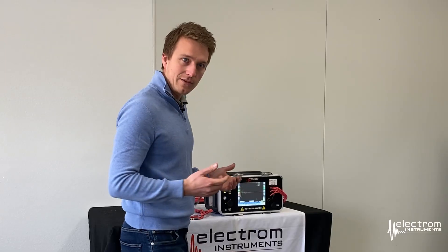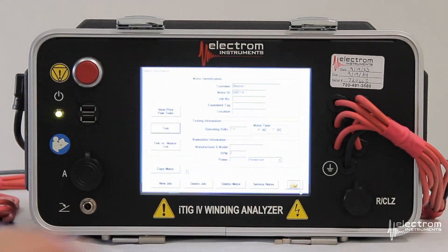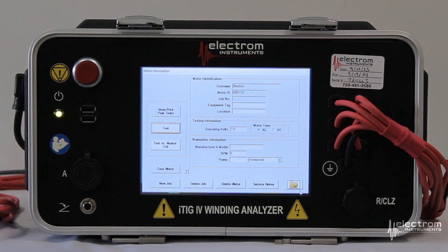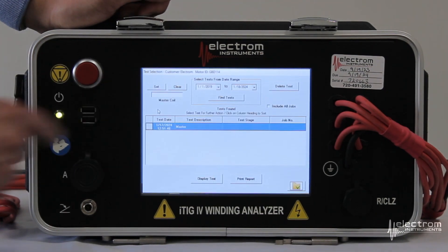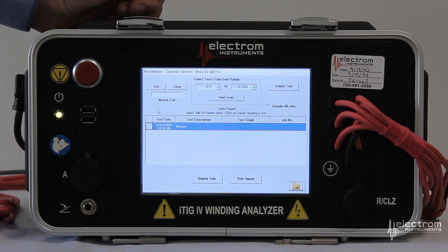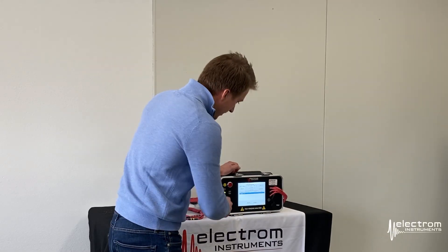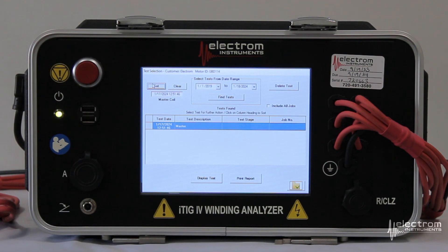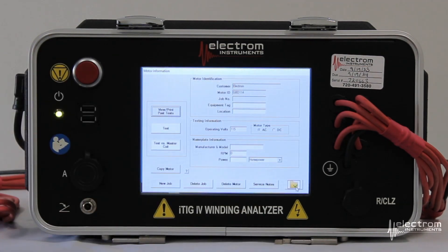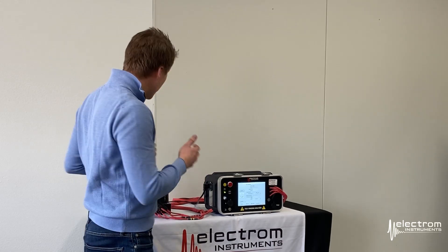Now we'll see what this looks like when we save it as a master. Click the folder button to exit test mode — everything is automatically saved. From here we go to View/Print Past Tests. We see the time and date stamp of the test record we just ran. Notice the test description field has the 'master' identifier in it. In the top left corner we now select to use this as our master, and it will enter in the time and date stamp of this master test. Hit the folder button to exit, and we are now ready to continue testing all other motors similar or identical to this one.